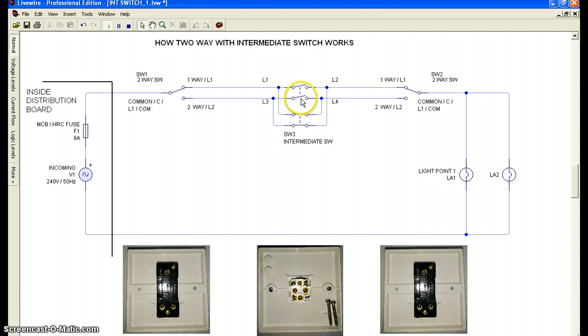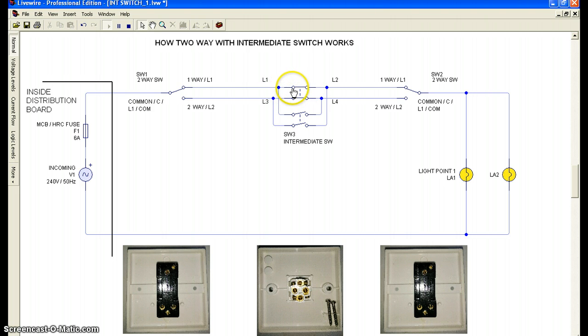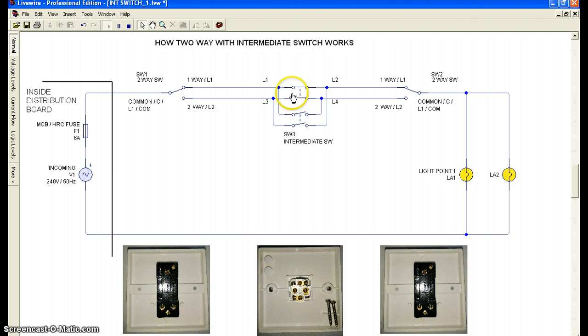In the second condition, L1 is connected to L4 and L3 is connected to L2 — that is a cross connection. So the two conditions inside an intermediate switch are: straight (L1 to L2, L3 to L4) and cross (L1 to L4, L3 to L2).